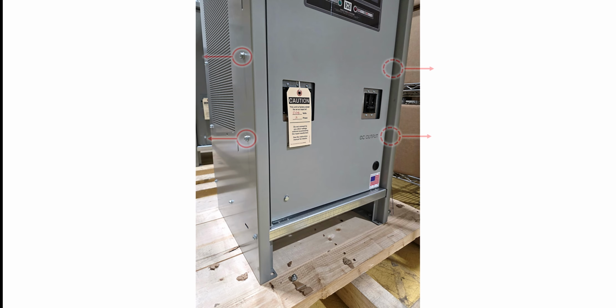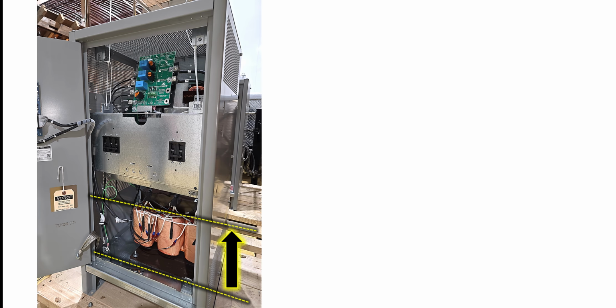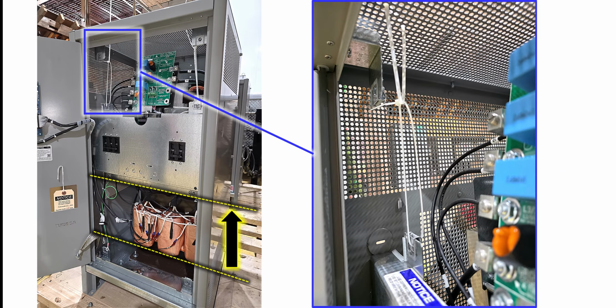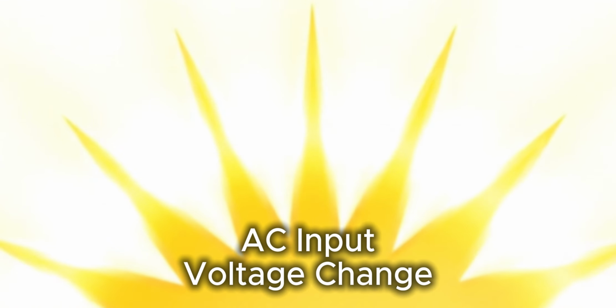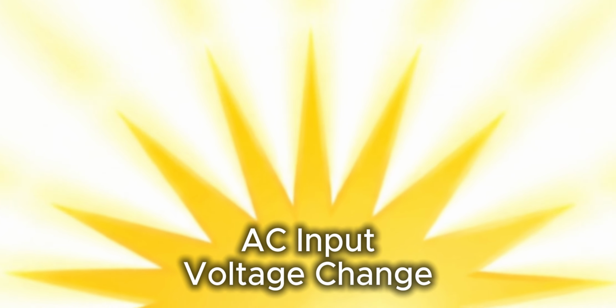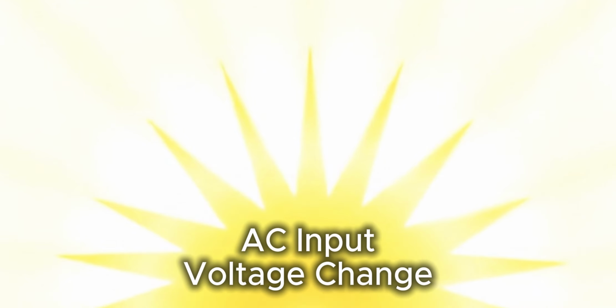While supporting the breaker bracket from below, remove both fasteners on each side of the charger that hold the breaker bracket to the cabinet. Lift the breaker bracket high enough to easily reach all of the connections on the primary side of the transformer. Use long zip ties to suspend the breaker bracket from the top of the cabinet out of the way of the transformer. Note, you may need to cut a few zip ties off other wires inside the cabinet to allow full range of motion.